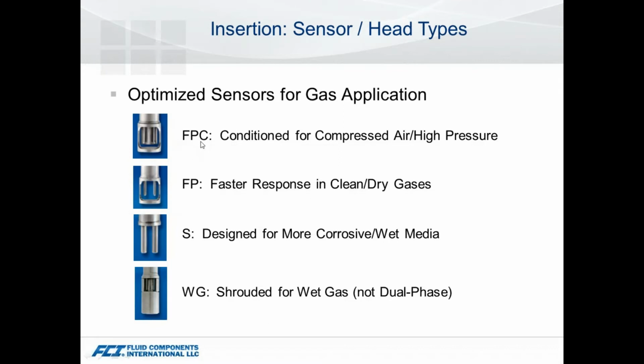The FPC is a very unique sensor within the industry. It was designed specifically for compressed air, higher pressure applications. We noticed that in certain conditions, there was a little bit of a decline in the reading at these higher pressure gases. So this sensor has this little conditioning plate built into it that's on the back side of the flow direction. And this basically just ensures we get good heat transfer between the heated RTD and the media flowing.